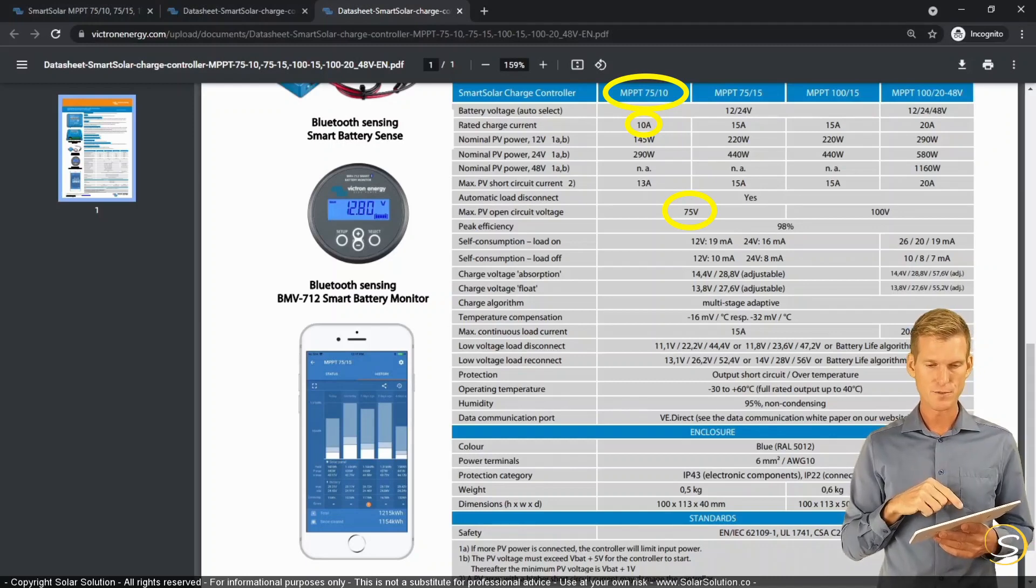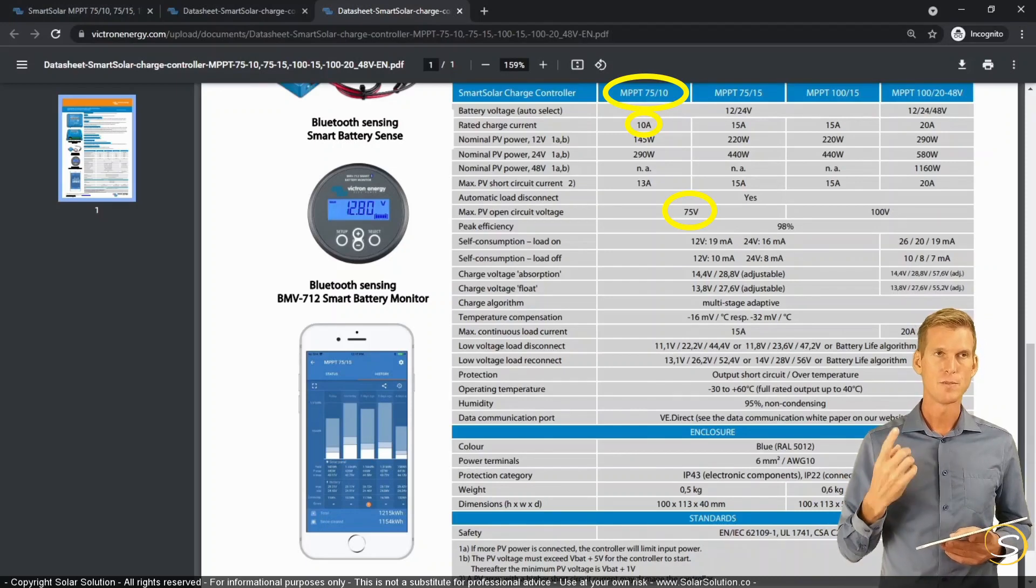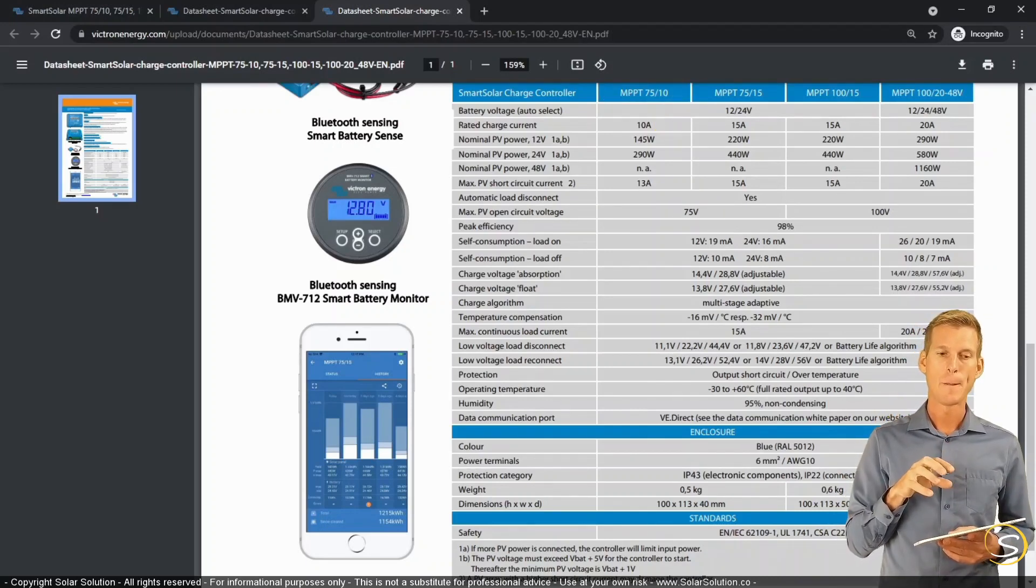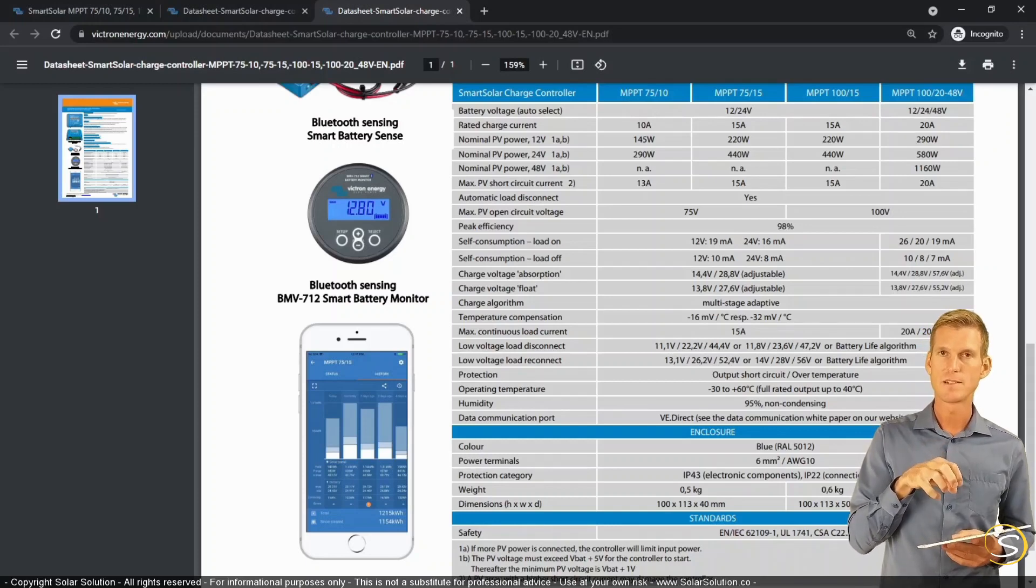And normally, you should never, ever exceed the open circuit voltage that is specific for certain charge controllers. So don't exceed the 75 volts in any kind of situation.